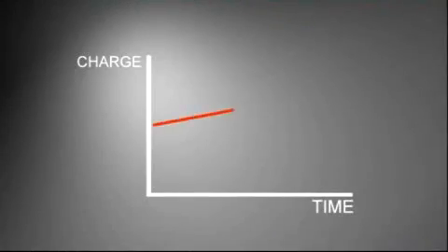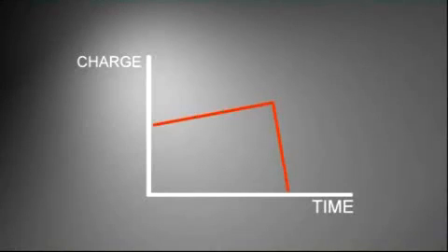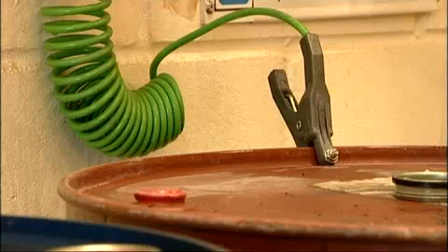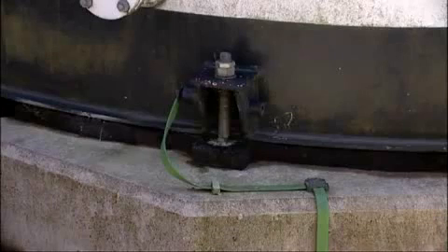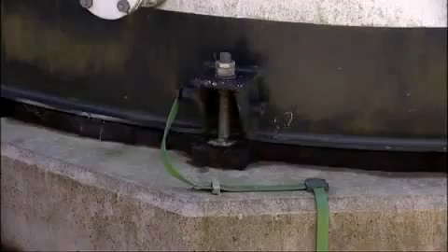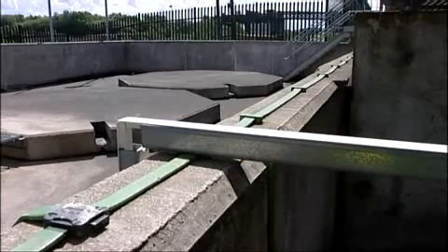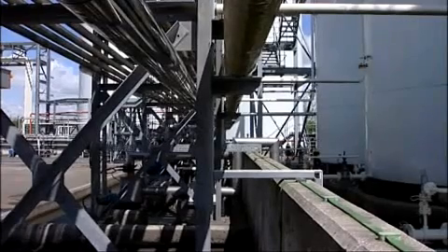Earthing establishes a continuous electrical path to Earth and will remove charge rapidly. Conductive equipment is connected to an earthing electrode or to the building earthing system in order to prevent sparking between conductive equipment and earthed structures. A bonding system connects various pieces of conducting equipment together to keep them at the same potential. Static sparking cannot take place between objects that are at the same potential.